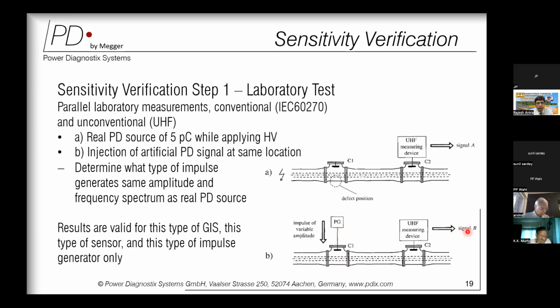Once we have recorded the same voltage and the same pattern, we conclude that the pulse generated by this artificial pulse injector has the same effect as the partial discharge which my original PD source would have generated. What we achieve is a pulse voltage which is equivalent to a 5 picocoulomb partial discharge. These results are valid for a particular type of GIS using a particular type of sensor and a particular type of pulse generator. They are valid for a particular setup.